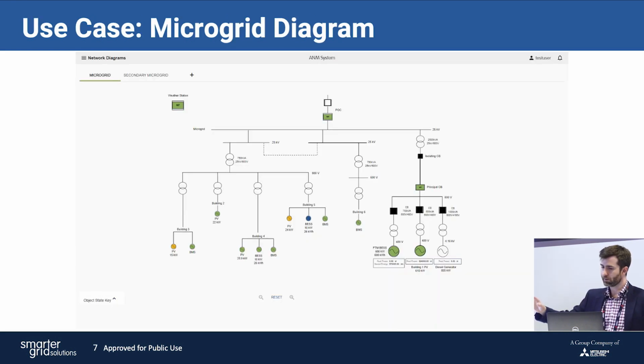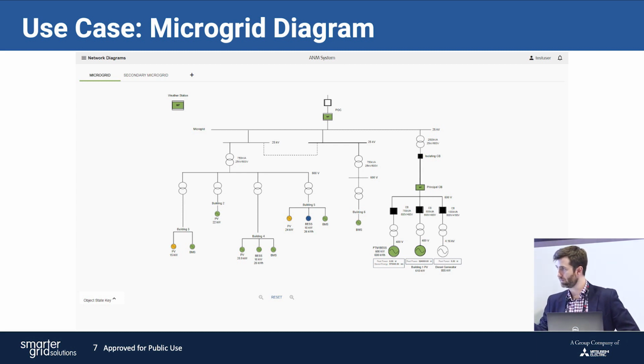Here's an example of what a microgrid might look like in our DERMS system. Each of these assets, especially the color ones, are color coded based on their current states. The yellow ones are currently curtailed based on real-time conditions, since we can't always be generating fully, especially if we're islanded. The green assets are generating fully, or at least in grid forming mode. We've got our diesel generator, colored white because it's not always connected. We get live status reports from all of our telemetry and switches, so we can manage the power in real time.